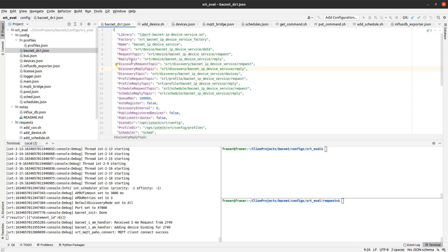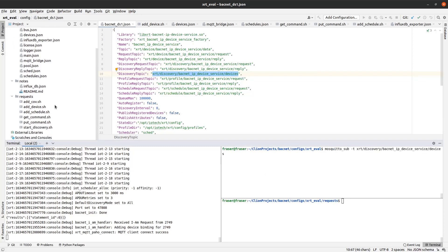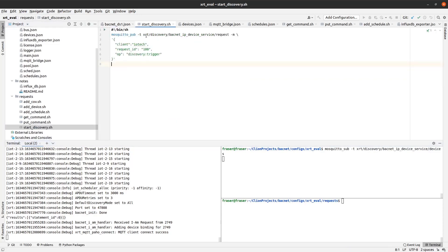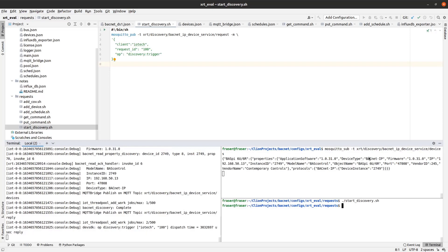The first thing that we're going to do is to use the discovery topic to send a message from an MQTT client to trigger BACnet discovery. From console one, I will start an MQTT client that subscribes to the discovery reply topic. From a second console window, I will issue an MQTT request to the discovery topic to start BACnet discovery. In the first console window, you can immediately see the metadata for the BASPi device that has been discovered.